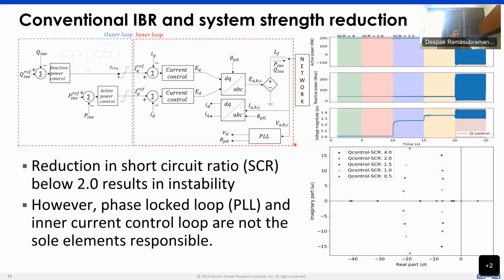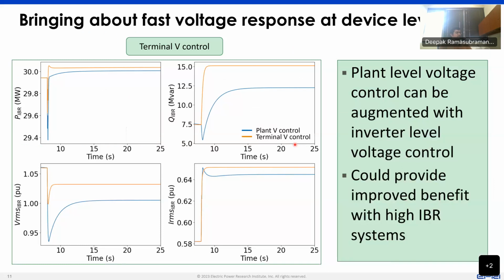Because if we consider an example now wherein we move this voltage control, which was at the plant level, down to the inverter level and make inverter level voltage control come about, we can have a response that, if you compare plant level voltage control versus inverter level voltage control, shows a drastic difference. You can see a drastic improvement in the type of reactive power that gets generated, and in the control of voltage that happens across the network.